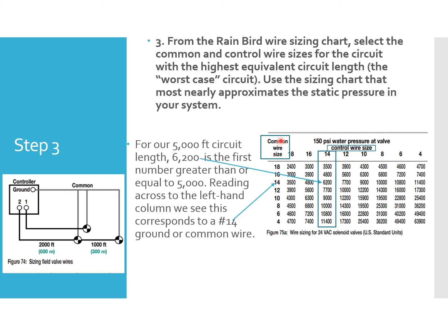So we're going to come down here and we're looking for the common wire first. So we're looking for the first one on the chart that has 5,000. Well, this one's close with 4,800, but not quite. We need it to go 5,000. So the next closest thing is the 6,200. So what that means is our common wire size meets right here. So our common wire size needs to be 14 gauge. Okay, and so then reading across this left-hand column, we need to find the same thing for that 5,000.